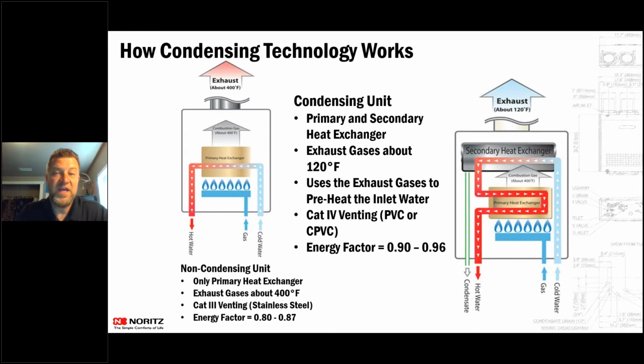With a tank water heater where you're like a 0.63 or up to like 0.70, so 63 or 70 cents is going to heat the water, but 30 cents of that is actually going out the flue. So the higher the energy factor, the more energy is going into actually heating the water versus going out the flue of the unit. Okay, and when you say going out the flue, is that just energy lost per se, just in the processes of?